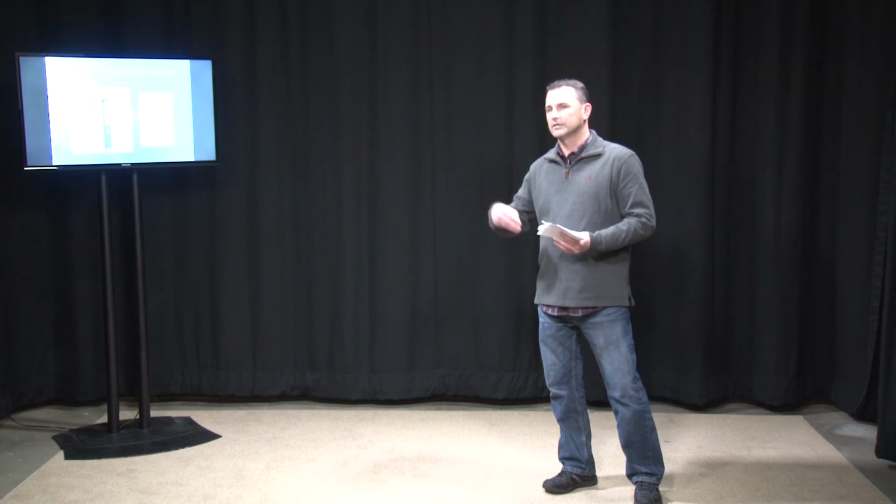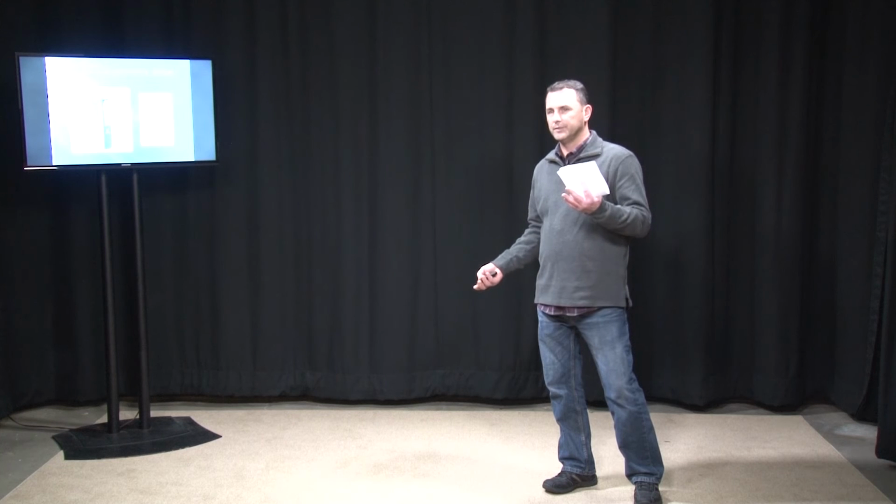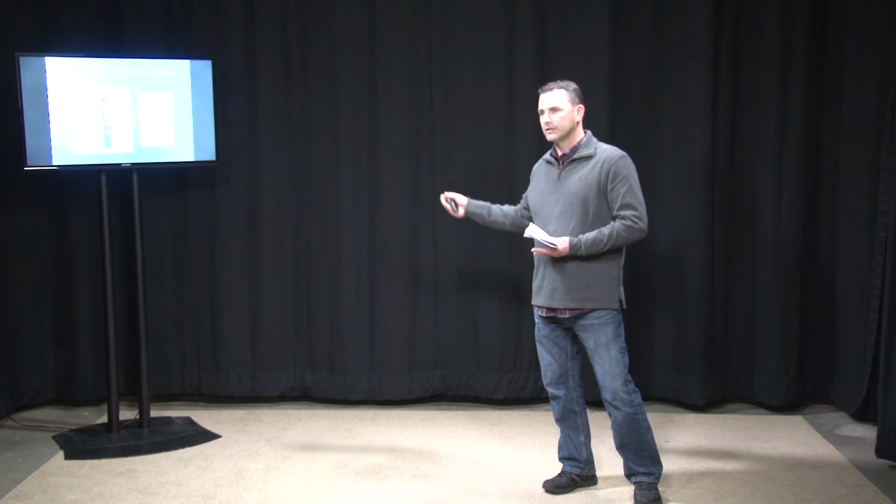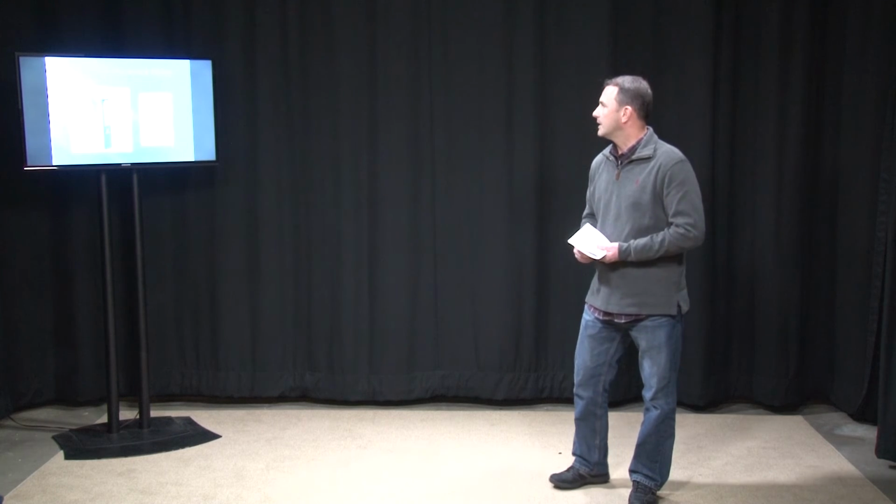Variable frequency drives. And on the right, I also have a starter in the picture there. But talking about the variable frequency drive, it's a way to slow the fans down inside the unit or speed them up, depending on dampers being closed, how many air changes they want to do in the space. You can speed up the amount of air discharging into the occupied space or pulling it out of there. Normally the safety relays will be tied into the VFD drives to shut down the fans based on the smoke or any other type of emergency case involved.